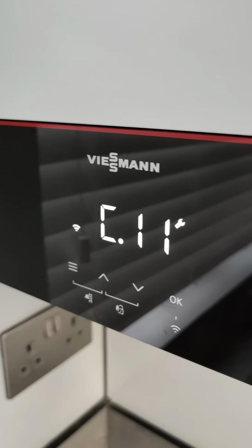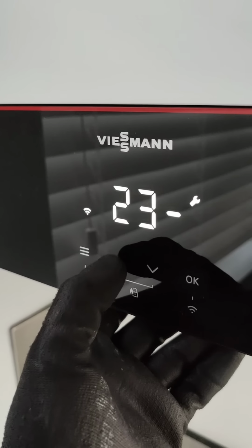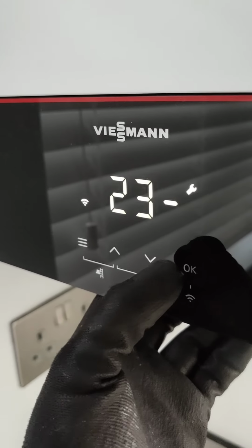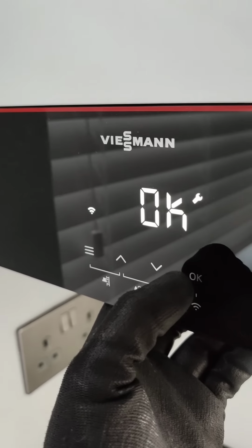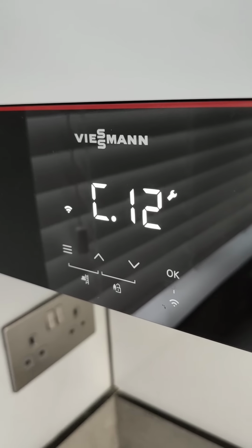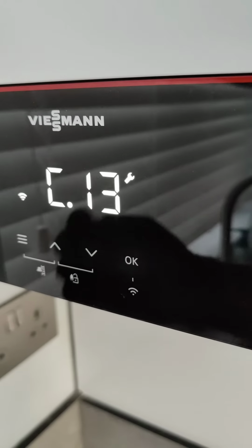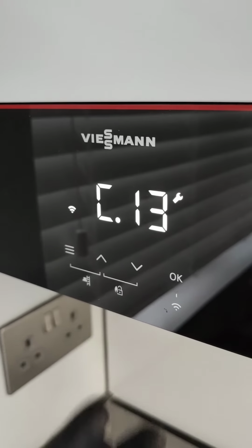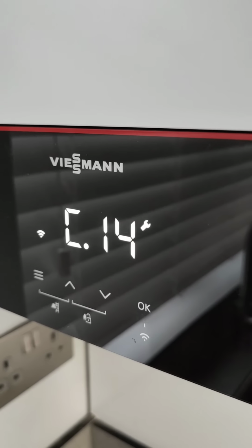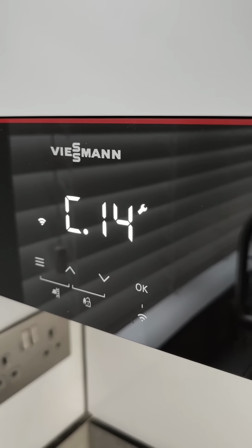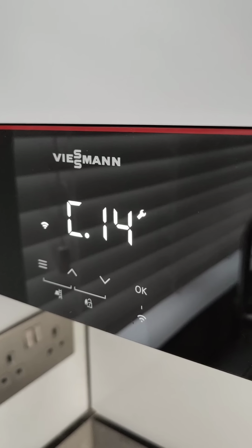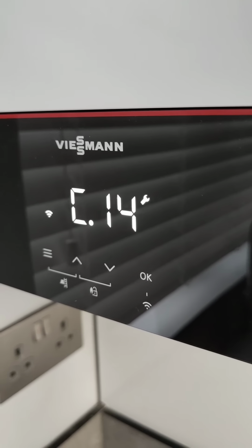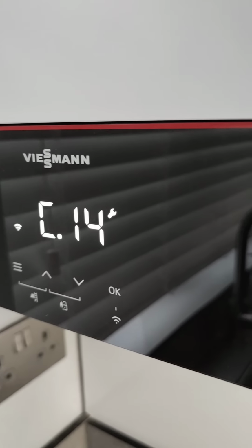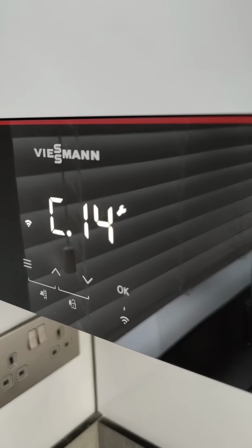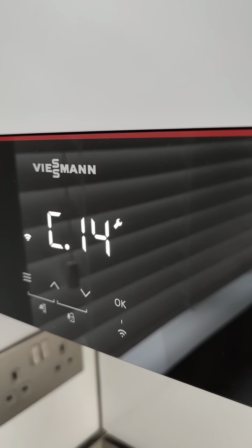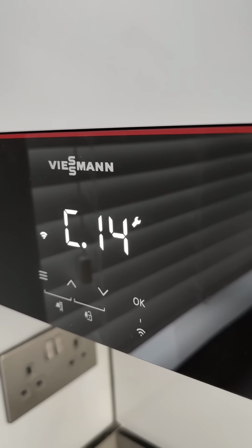C11 we can set the date and the day, so it's the 23rd of the 12th 21 today. C13 is automatic daylight saving on and off. C14, that's the plug in the boiler which we connect the thermostat up to, and we can also use it for different things. It's called plug 96, so we could use it for circulating pumps, external demand, external blocking.